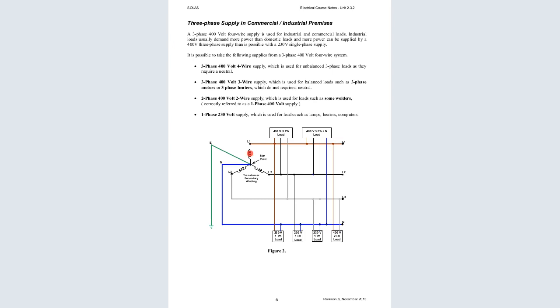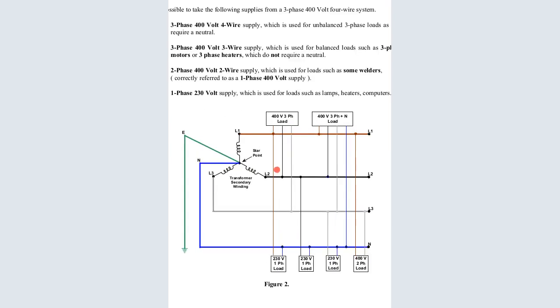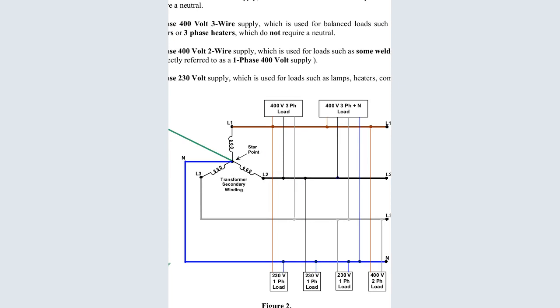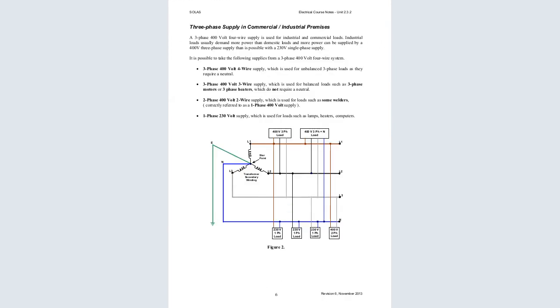That is line 1, you can see its resistance here. Line 2, you can also see its resistance here. And then line 3, also its resistance is here. So when the 3 wires, when the 3 lives meet at this point, that is called a star. It is called a star point. You can see that arrow. Let me zoom out so that you guys can see. This point here is the point where the 3 phases meet. It's called a star point. So the star system is meeting at this point, and we can now tap our neutral from this point. At the same time, we can tap our earthing. This is the earth. The earth is in green. We can tap our earth from this point.